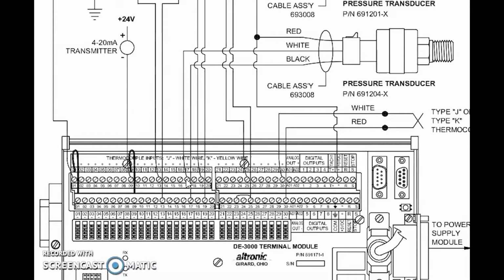Pulsation, fluid shock, etc., those types of things can damage any industry standard pressure transducer, and they should probably be replaced at that time. Another thing that can cause a pressure transducer to not read properly is the voltage supply. If we have a weak connection or a loose connection somewhere and we're not getting a true 5 volts to that pressure transducer, that can cause the pressure transducer to read low. Likewise, that ground wire is very important.